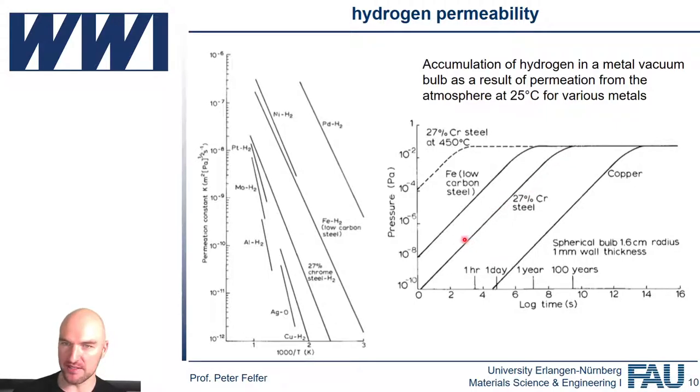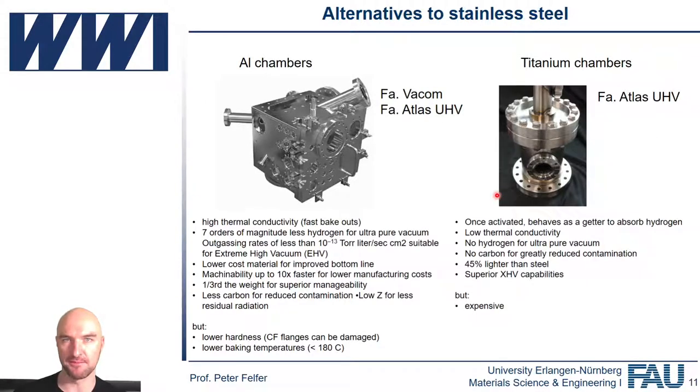And this is essentially the reason why we're always measuring hydrogen in atom probe tomography. Not because it's in your sample, but because it permeates from your stainless steel, which has a certain amount of hydrogen in it, which is not in equilibrium, so it wants to get out. And it can diffuse into the vacuum chamber and then just live there. Essentially, in the stainless steel it sits there as an individual atom. Then it just plops into the chamber and then recombines to H2. It can't leave just as a single hydrogen, but as H2 it leaves and then it adsorbs somewhere.